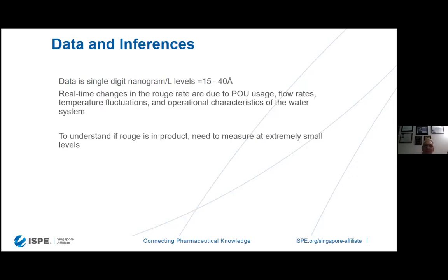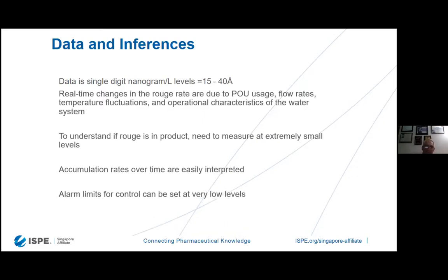Accumulation rates over time are easily interpreted because you have a way in order to accumulate that data, in order to show it in either a graphical format or actually in actual values on screen. Alarm limits for control can be set at very, very low levels. It's very important to understand that we can set the alarm limits for whatever we need to, but it should be something that's assignable and makes sense based upon how you operate your system at its given temperatures, flows, etc. So you should always use a scientific assessment in order to show when to do your derouging passivation.